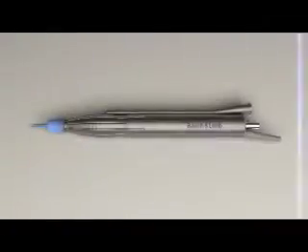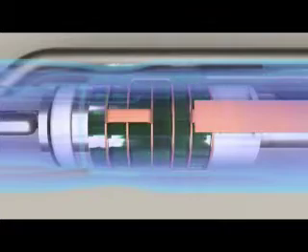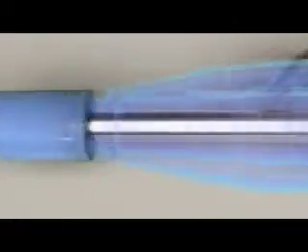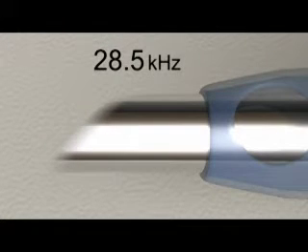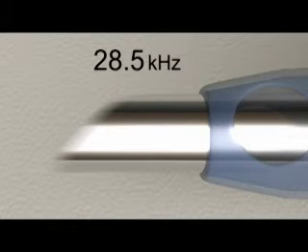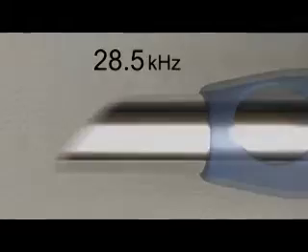Stellaris has matched these improvements in fluidics with a novel six-crystal handpiece. The stroke length is 25% longer to enhance mechanical nuclear fragmentation. It operates at an ultrasonic frequency of 28.5 kHz, chosen to optimize the cavitation emulsification of nuclear fragments for efficient lens aspiration.